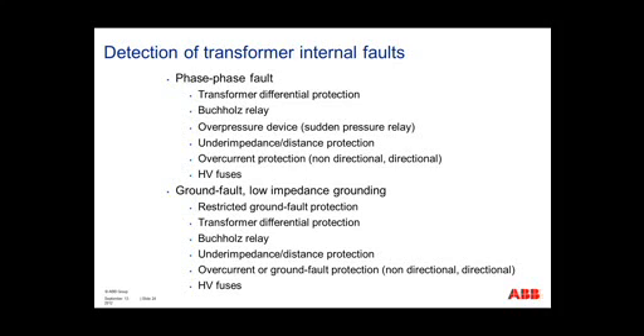Also, another mechanical device inside the transformer is your overpressure device, or your sudden pressure relay, or SPR. It works on the same basis of oil breaking down, causing gas. This gas expands, causing pressure inside the transformer. Your SPR relay will sense this pressure and trip off the related breakers. As backup protection, you have your distance protection, your overcurrent protection, and your high voltage fuses. Typically, this is backup protection because your distance, your overcurrent, your fuses need more current to sense the fault. And if that current is present, that could damage the transformer. That's why you don't use it as a primary form of protection.